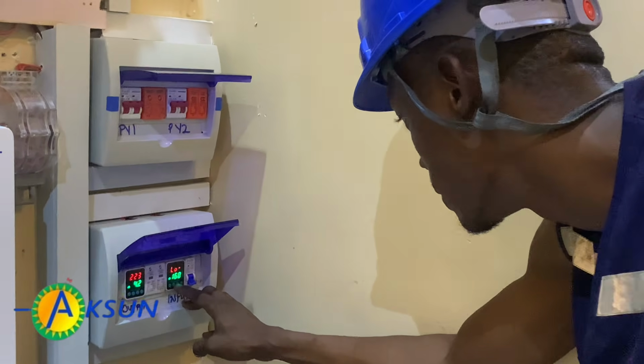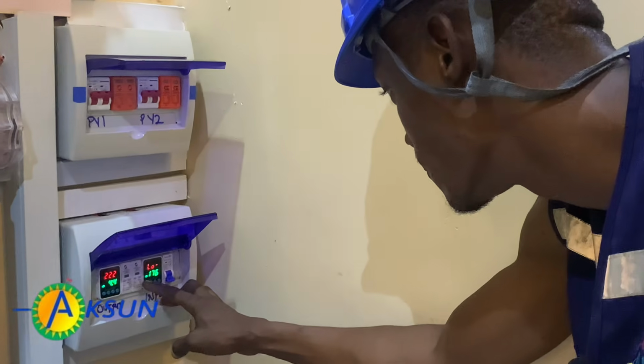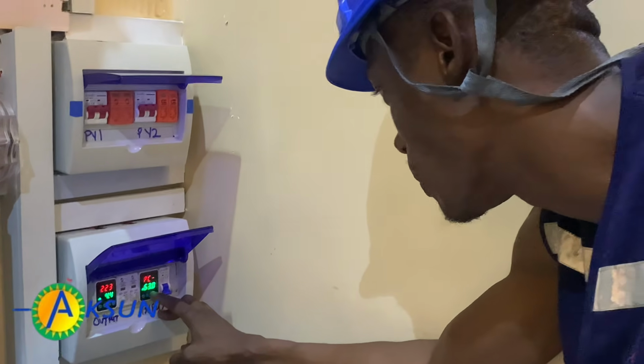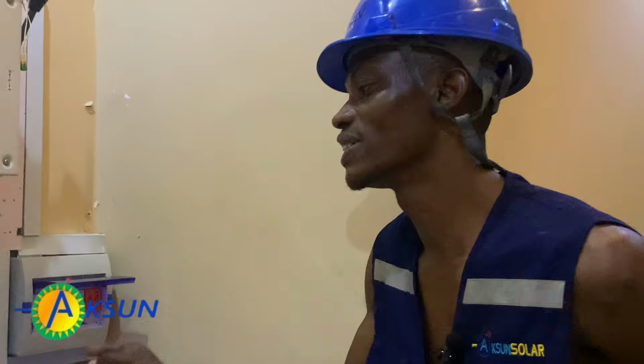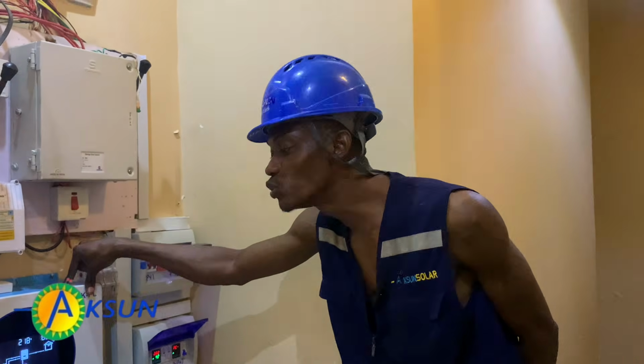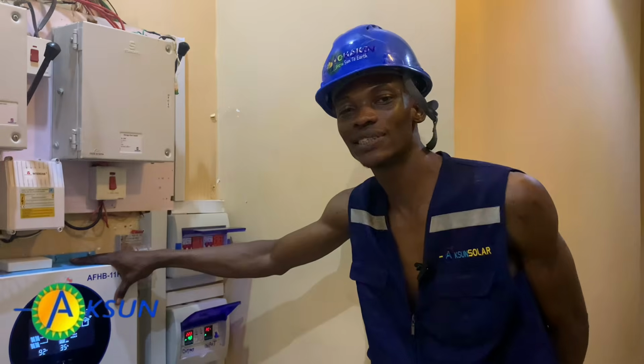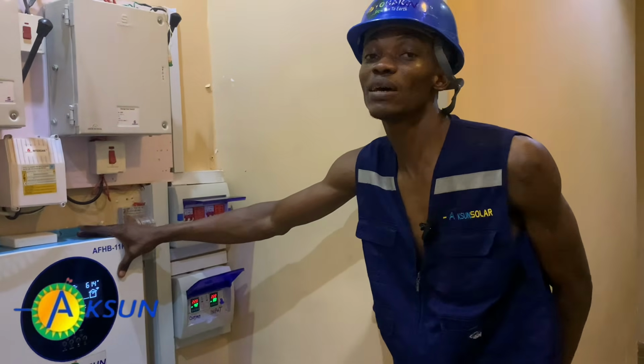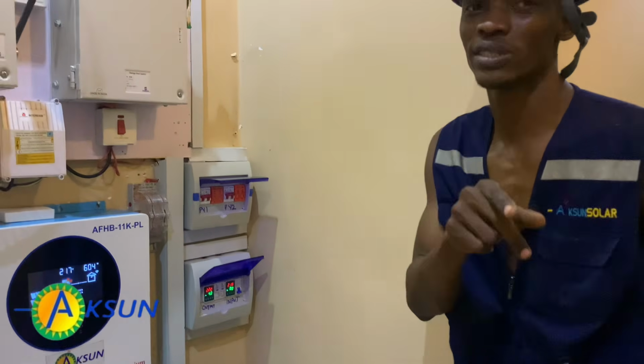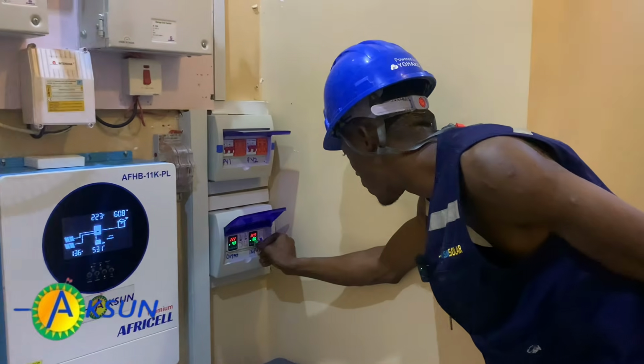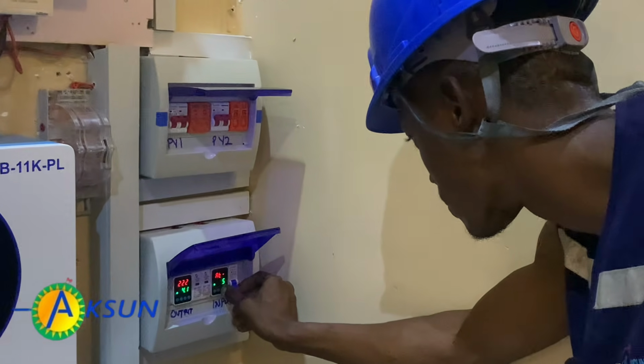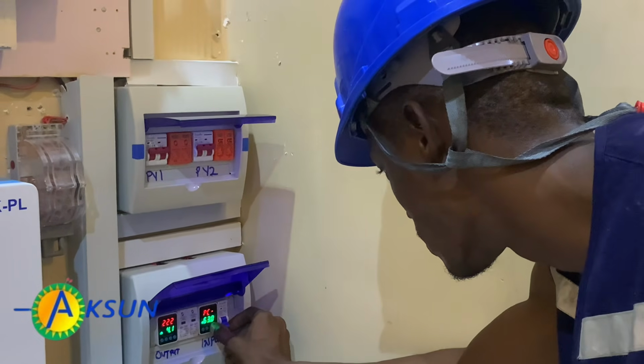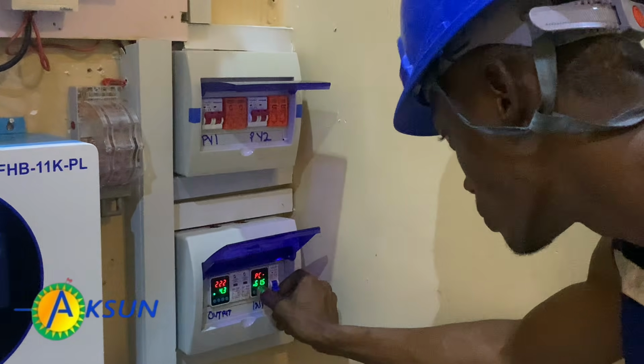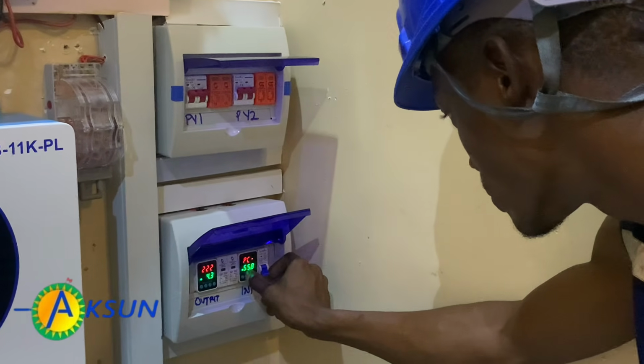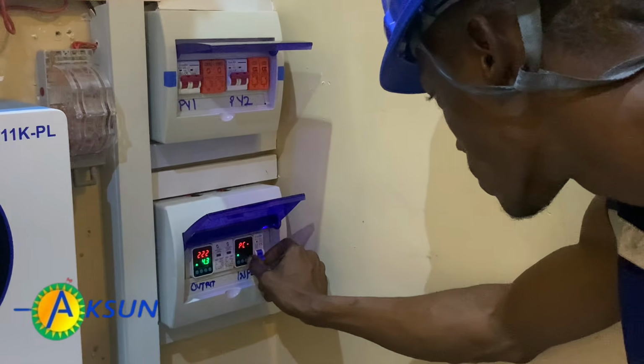For overvoltage, undervoltage, 180. And then for my current for the grid input, remember we are going to be adding our load together with the current for charging. Remember we set it to 10 amps. So if I add 10 amps to 45, which is the maximum for our load, that is 55. So we'll be using 55 as our current here. So that's that for our setting.